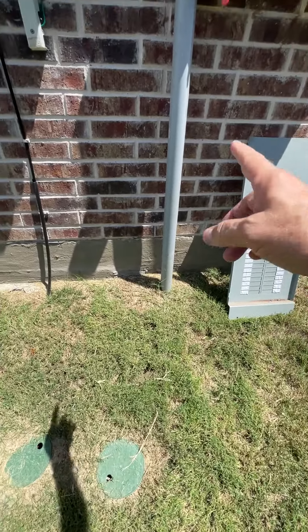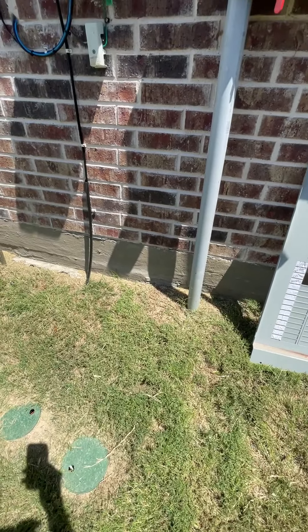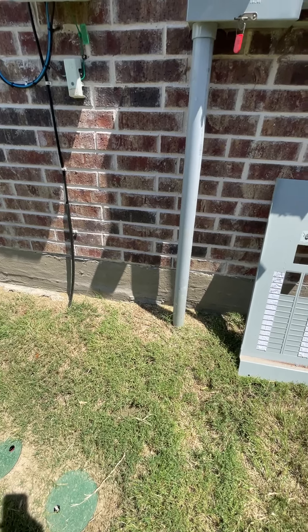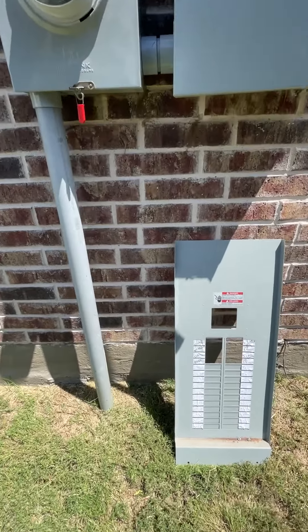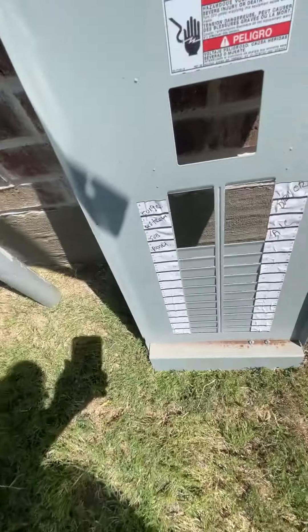I see that in a lot of new construction. I don't know if a slip joint is an absolute code requirement, but it seems to be industry standard. Coming along here, this is the main grounding wire coming in, buried into the ground, and it has been labeled.